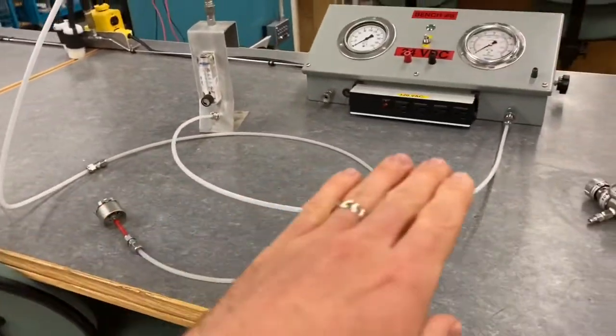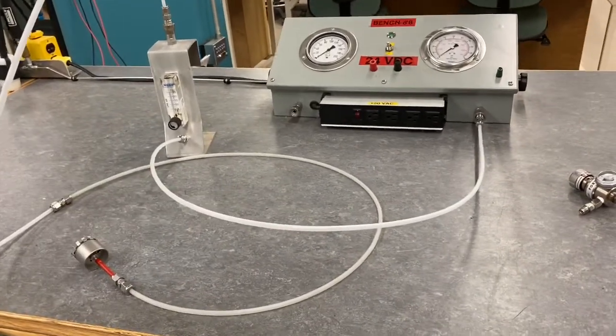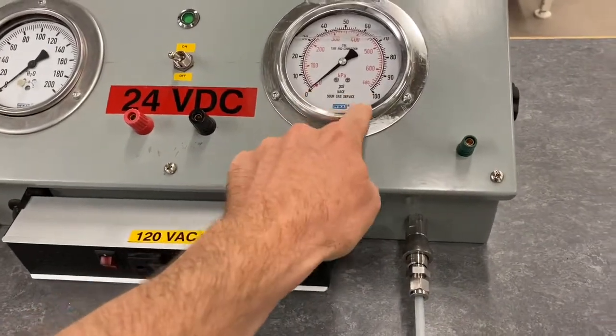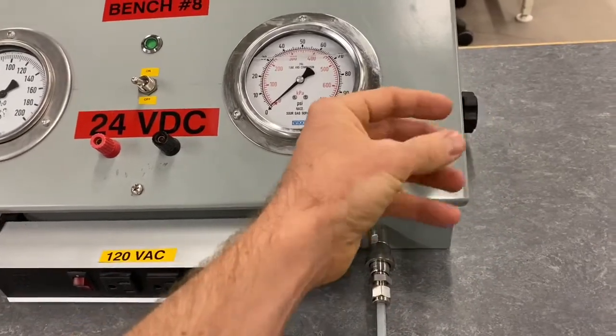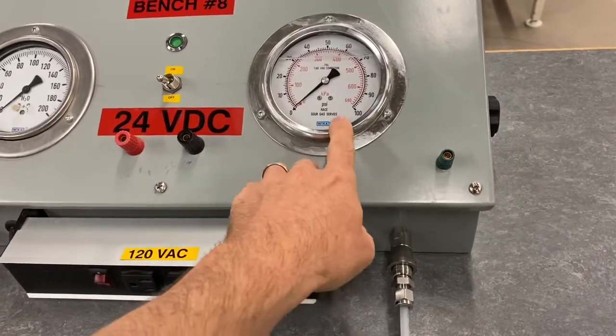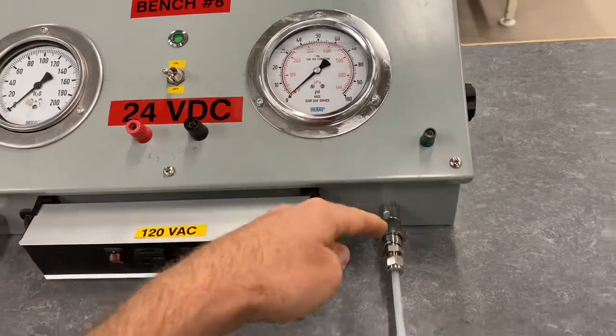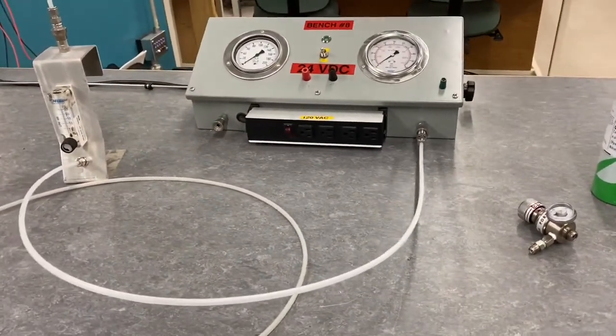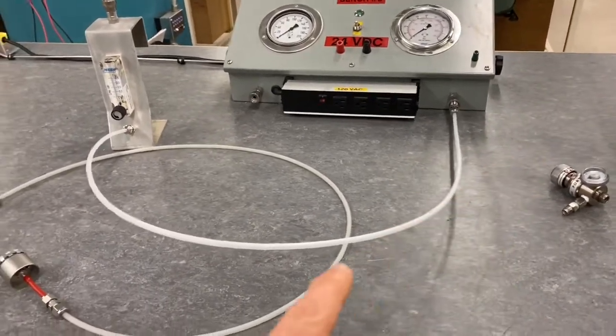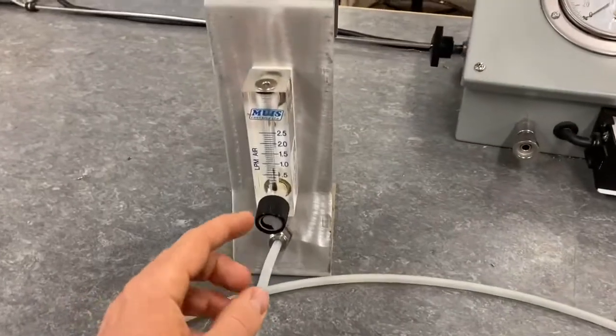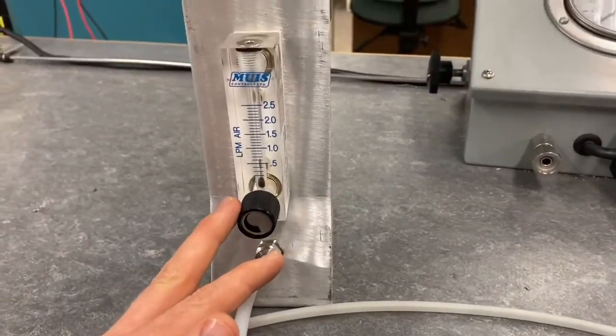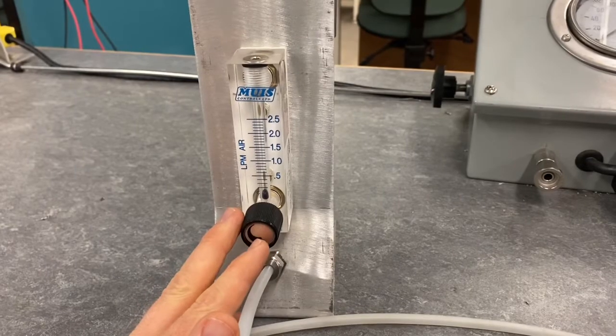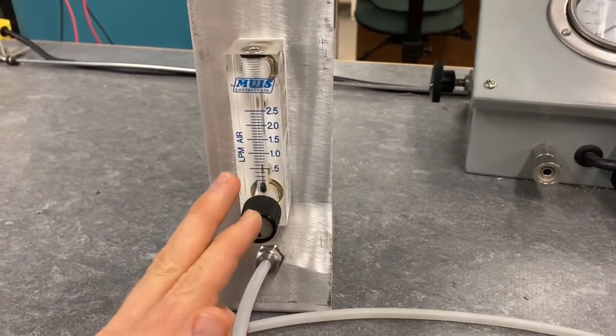If we move over here now, all this white plastic tubing is connected up to our instrument air. We're going to be increasing the pressure on this gauge. There's a regulator on the side of the bench. We thread that in and it's going to allow gas to flow out and regulate the pressure here. We only need about 5 psi probably, so that'll also reduce our pressure hazard of compressed air. It's going to flow out and over to a flow meter right here. This flow meter we're going to use for both the H2S and for the zero air we're going to use for zeroing the meter.